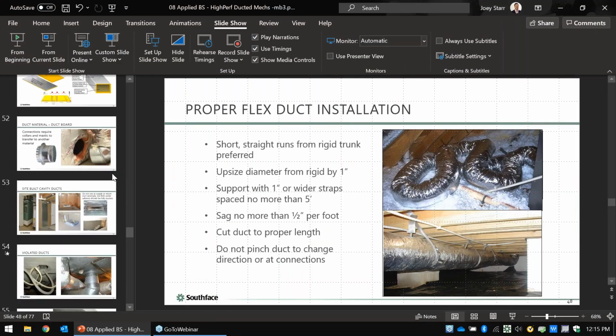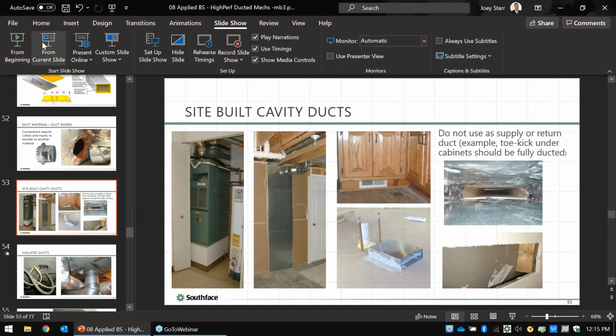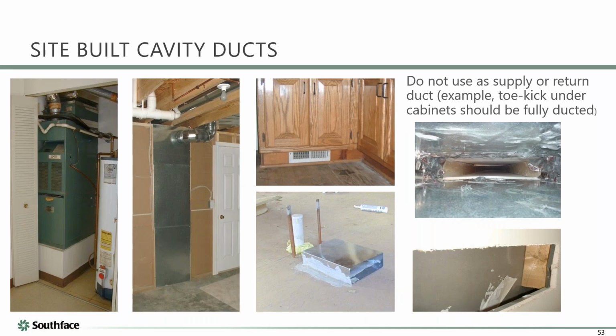Go after your ductwork. And like I said, pull the registers, because it's easy, especially in the floors. It seems like in a lot of the homes we're working on, the registers are in the floor and the system's in the crawl space. You can usually get to the air handler. So even if all you do is pull the registers and seal the boots as far in as you can reach, work your way out, and then seal all the places at the air handler, and we talked some about that filter lock, a magnetic filter thing, those actions alone, even if you can't get to the wyes and things like that, just doing the air handler and the boots will be huge and very impactful.